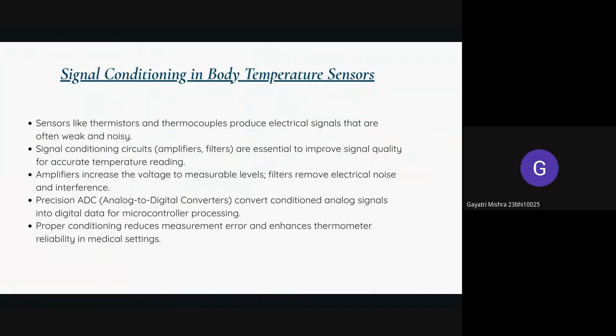This is Gayatri Mishra. Now I'm going to explain about signal conditioning in body temperature sensors. Sensors like thermistors and thermocouples produce electrical signals that are often weak and noisy. Signal conditioning circuits, amplifiers, and filters are essential to improve signal quality for accurate temperature reading. Amplifiers increase the voltage to measurable levels, and filters remove electrical noise and interference. Precision ADCs, that is analog to digital converters, convert conditioned analog signals into digital data for microcontroller processing. Proper conditioning reduces measurement error and enhances thermometer reliability in medical settings.